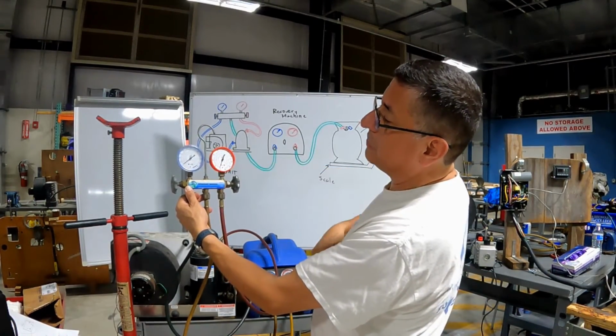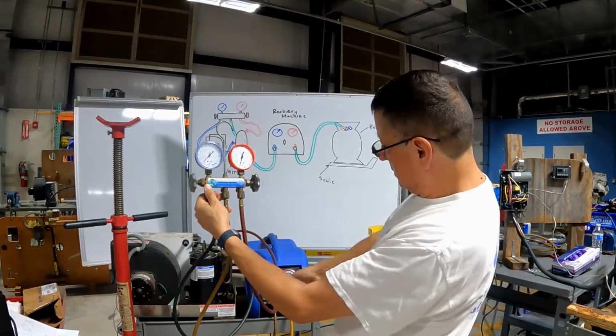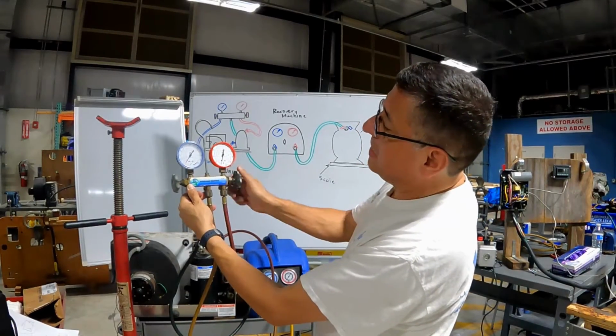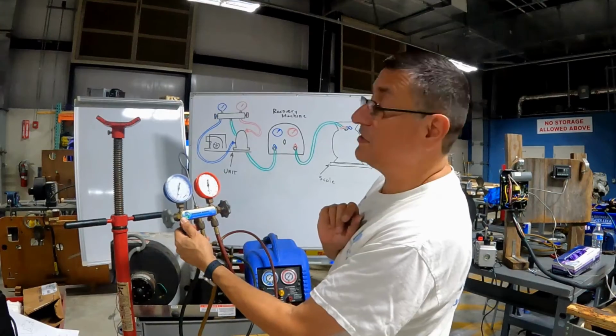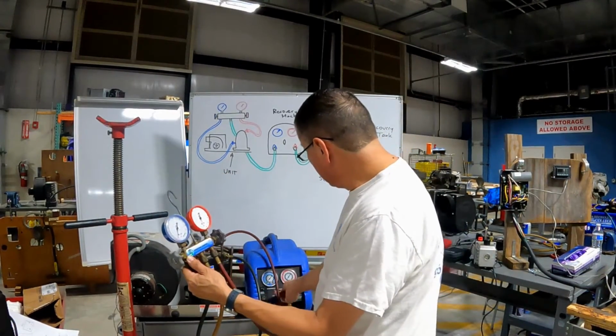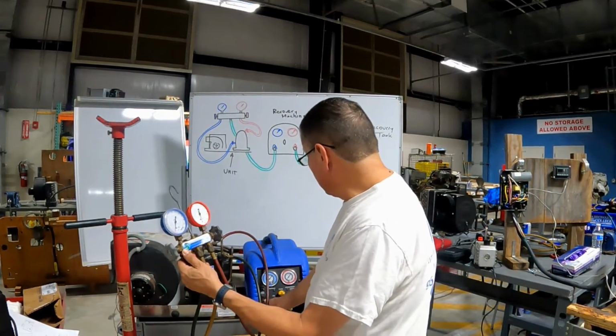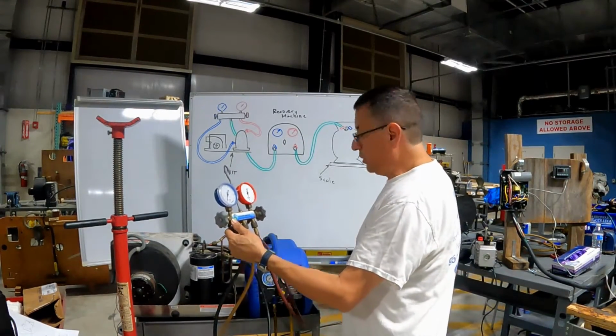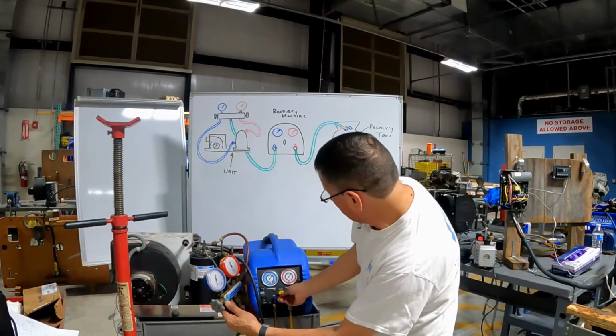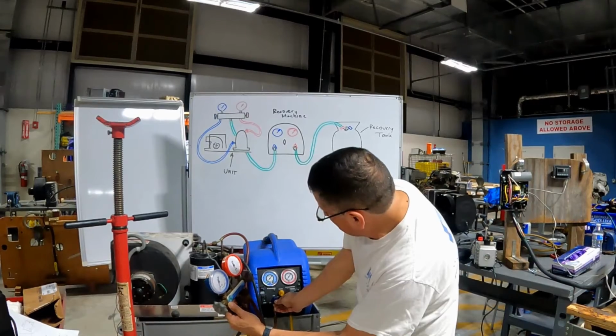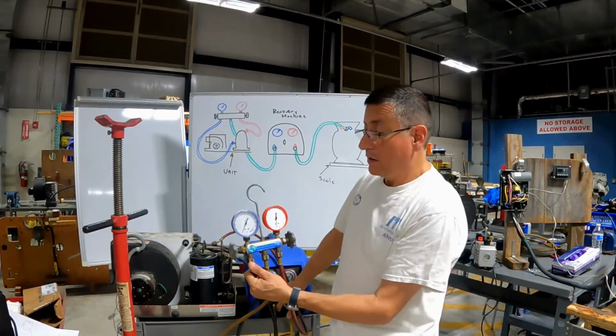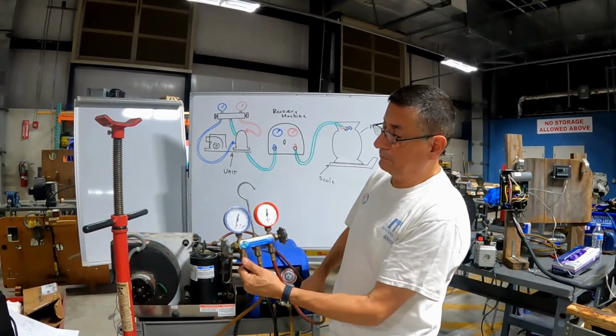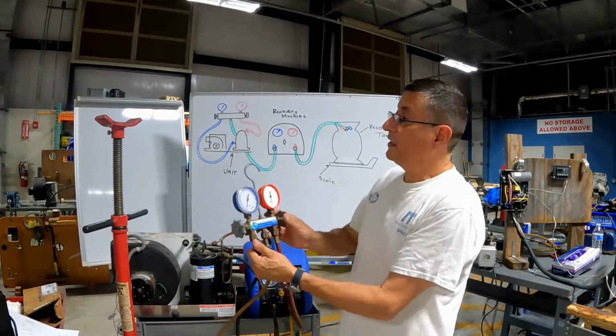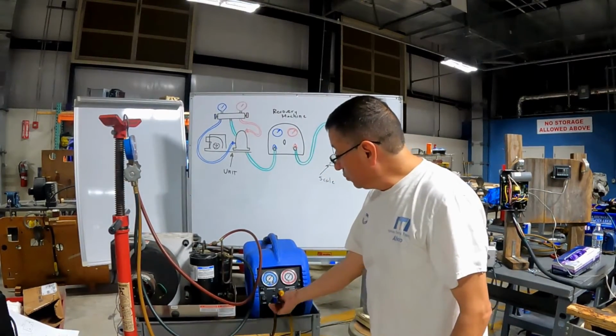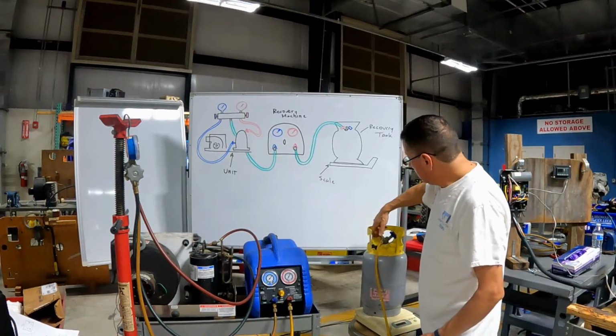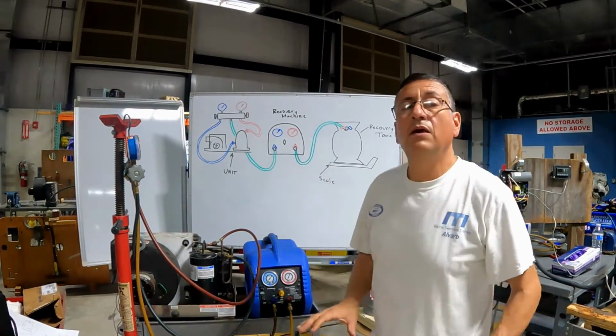The needle is going down, down, down. It's down. Okay, now the equipment finished. And we are going to turn off the valve. We are going to stop the equipment, and we are going to purge the system. We are going to select purge, and we are going to open both valves, and we are going to start again. The system stopped by itself, is properly purged, and right now the system is ready. I am going to close the valves, close the valve on the cylinder, and the system is fully recovered.